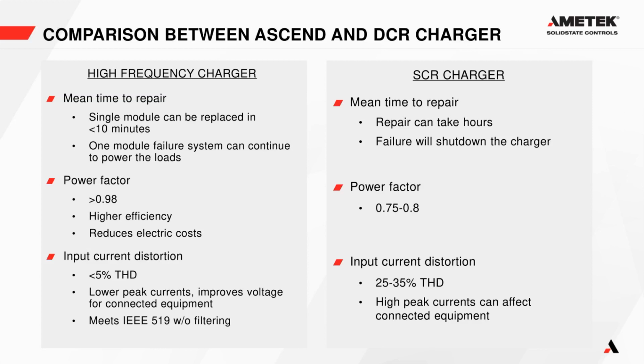And the Ascend 3-phase charger doesn't have a large input transformer like our DCR system would. It has a very small, high-frequency input transformer that provides isolation. The module weighs 25 pounds, as compared to our DCR transformers, which weigh hundreds of pounds each. So the Ascend 3-phase module is small and lightweight and easier to install and move around.